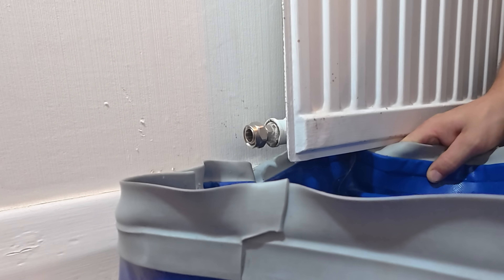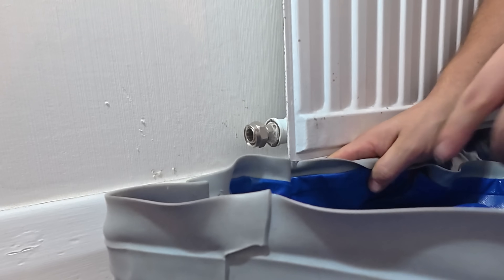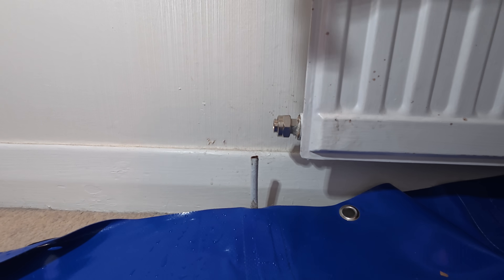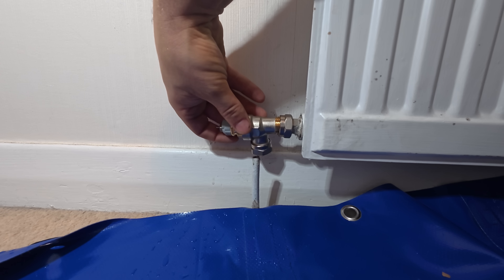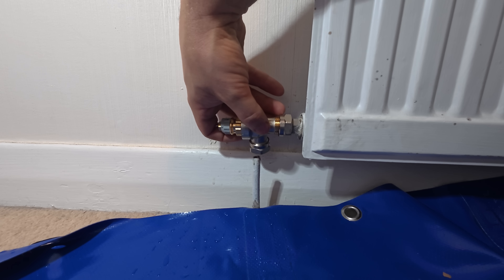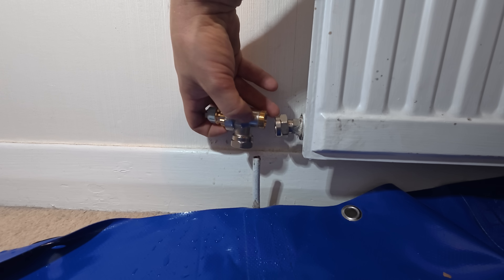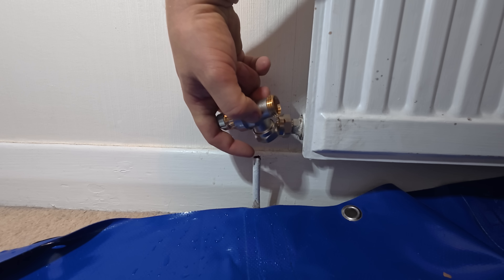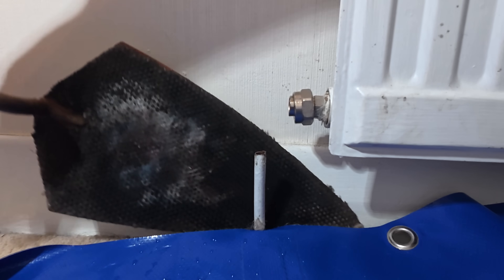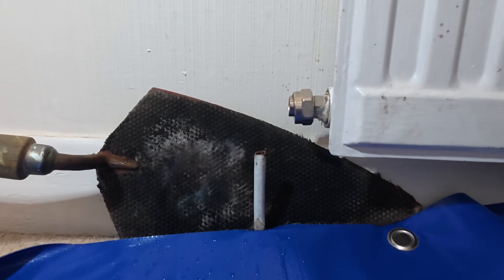Hopefully this is going to behave itself. We can take the tray away as I want a bit more access for soldering. We'll position the radiator valve to match all the rest, flux and paste up on the end, knock this back a bit, get the olive as far down as possible, then stick the reducer on and push it down. I'm going to protect the wall using my burn mat and take off the paint using the blowtorch.